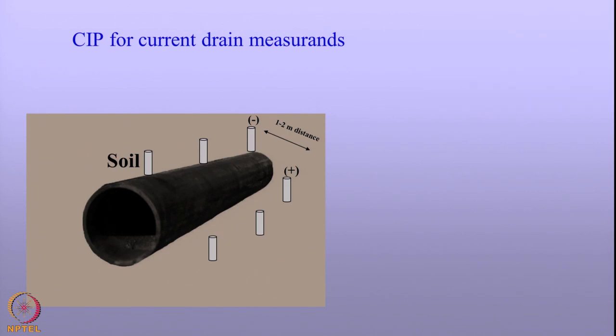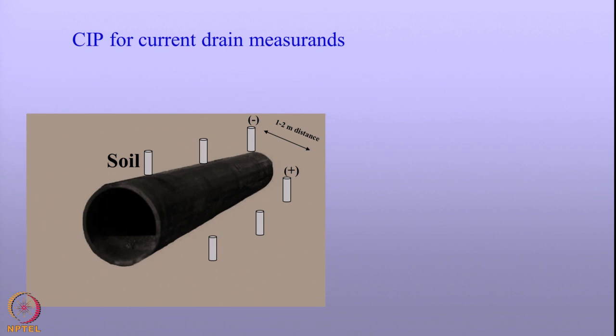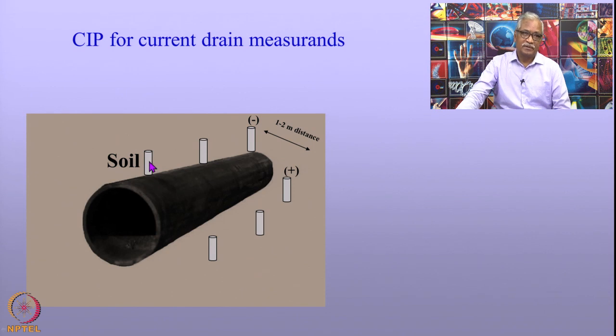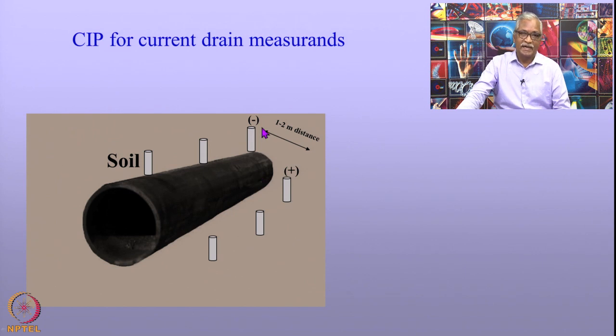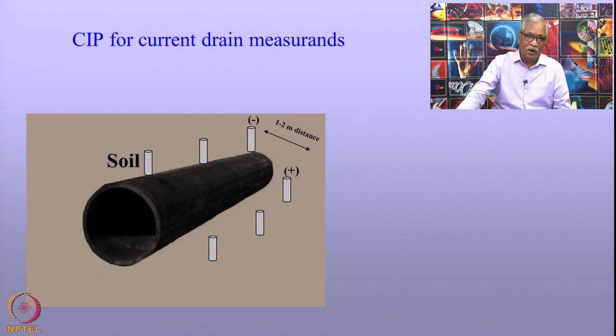Another type of close interval potential measurement uses one electrode kept well above the pipeline and the other on either side at a distance of 1 to 2 meters. The potential is measured between these two reference electrodes. If this potential is positive, current enters in one direction; if negative, in the other direction. The advantage of this technique is you can determine whether the pipeline is receiving current or acting as a drain where corrosion occurs.